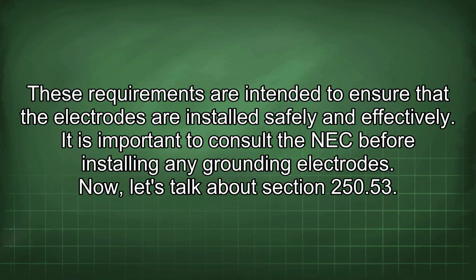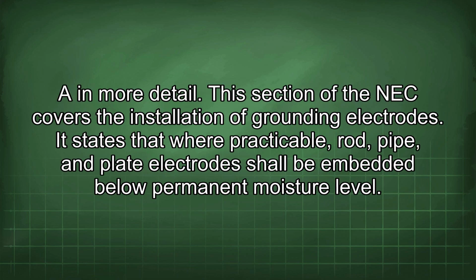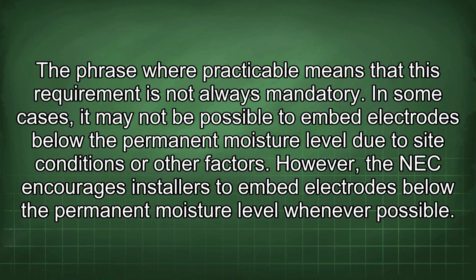Now let's talk about section 250.53 in more detail. This section of the NEC covers the installation of grounding electrodes. It states that where practicable, rod, pipe, and plate electrodes shall be embedded below permanent moisture level. The phrase "where practicable" means that this requirement is not always mandatory. In some cases, it may not be possible to embed electrodes below the permanent moisture level due to site conditions or other factors. However, the NEC encourages installers to embed electrodes below the permanent moisture level whenever possible.